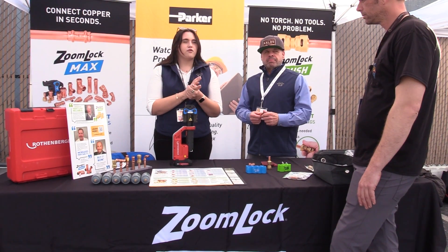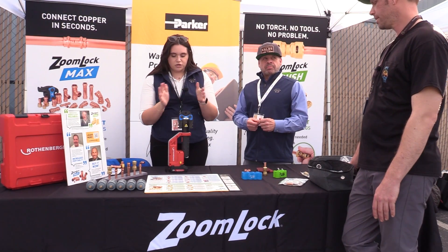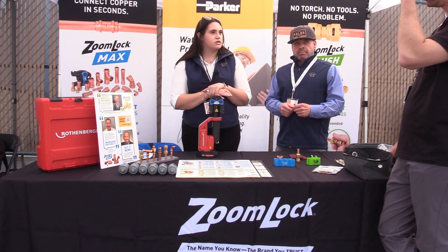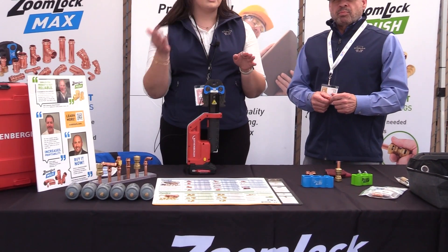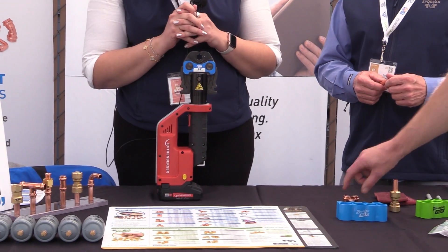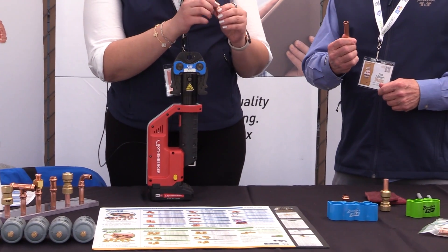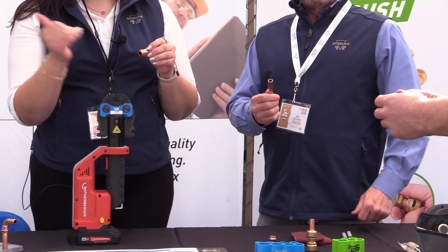Braze-free has been around for a while in the plumbing world — ProPress, SharkBite — but now we're bringing it to the HVAC world. So here we got ZoomLock Max. It's our press-to-connect fitting. You're going to use a tool and just have jaws to crimp the fitting onto the pipe. The jaws are going to crimp once before, on, and after the O-ring — that's a three-point press, ensuring a leak-free seal every time. You can see that O-ring inside, and there's a tube stop in there as well. When you go to slide your tube on, it'll stop itself, but we also have a depth gauge which we'll show in a second.